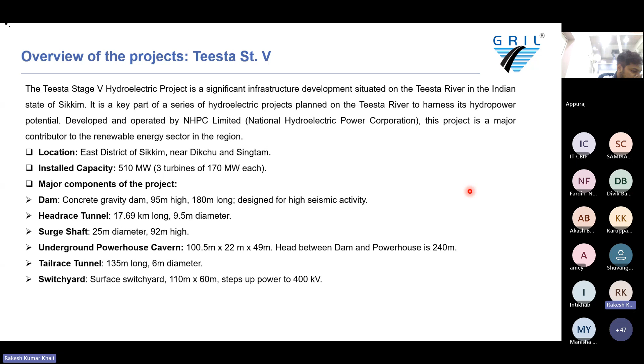Surge shaft 25-meter dia, 92-meter high. Underground powerhouse cavern 100 by 22 by 49. Head between the powerhouse and dam is 240 meter. Tail race tunnel 135-meter long, 6-meter diameter, and surface switchyard is 110 by 60, stepping up power to 400 kV.